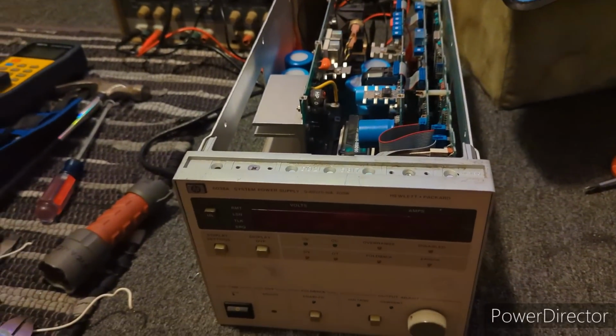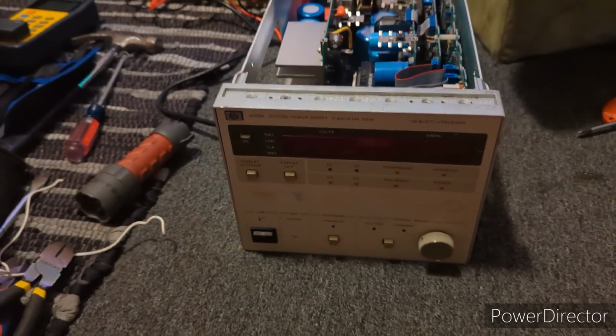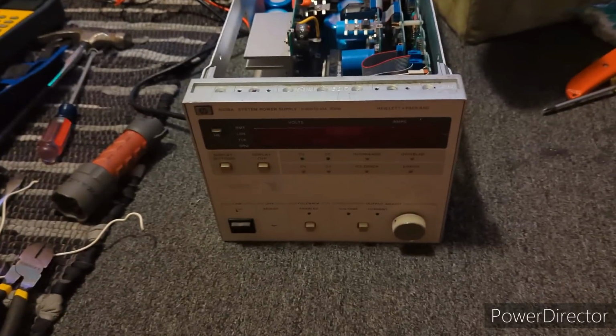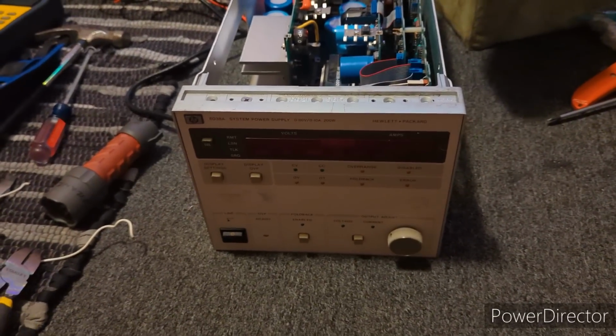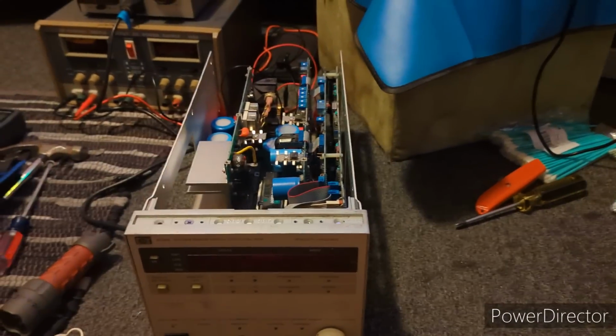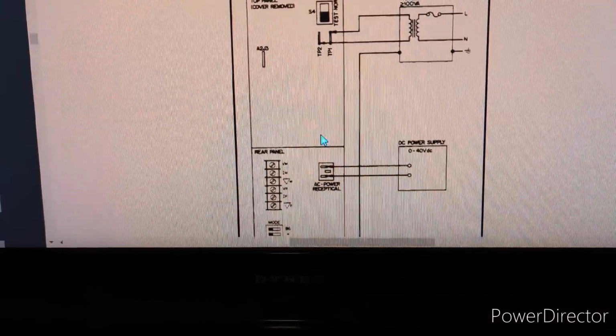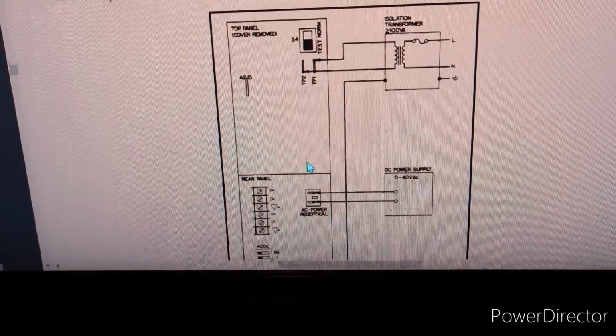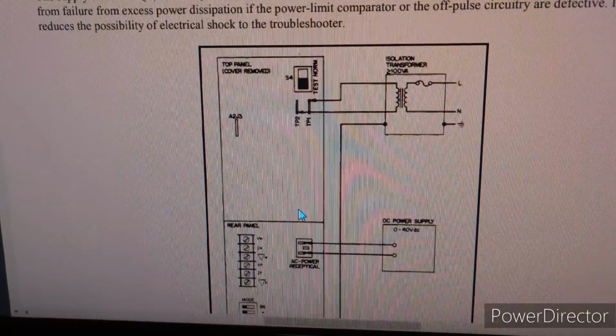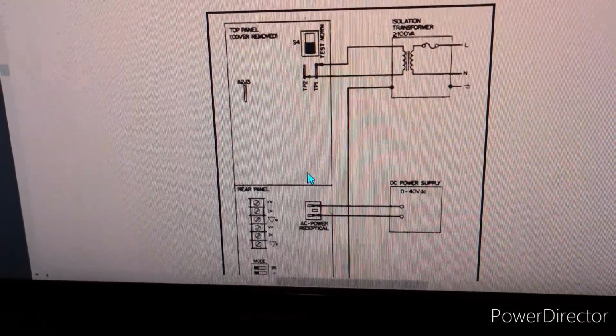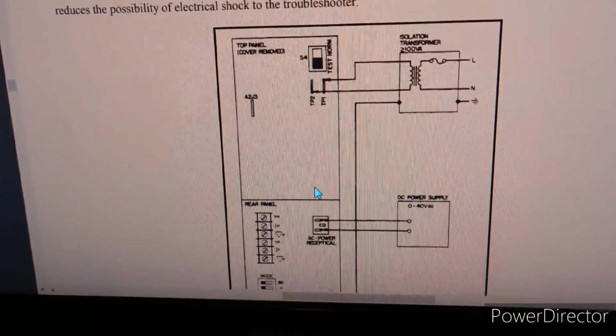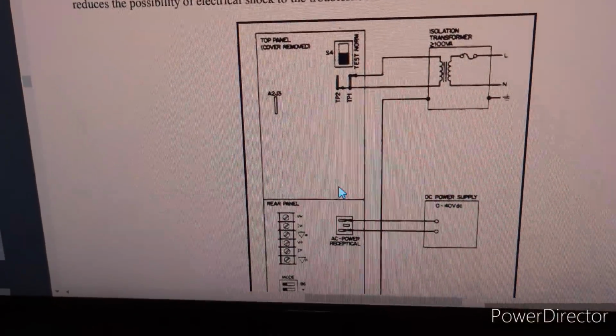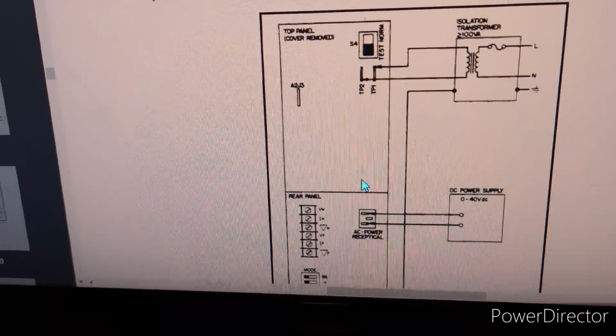Alright, so I've got the thing pretty much back together, so we can do some testing and see if it powers on. Initially I was just going to power it up normally using an isolation transformer, of course, but the service manual provides a setup that you can do for troubleshooting. This is the diagram that's in the service manual. First, they've got the isolation transformer, but it's not hooked up to the mains input. They have the secondary side of the isolation transformer connecting to test point 1 and test point 2 on the main board.